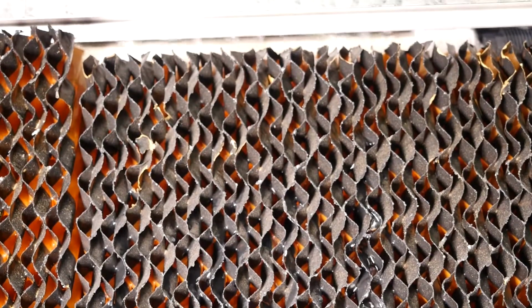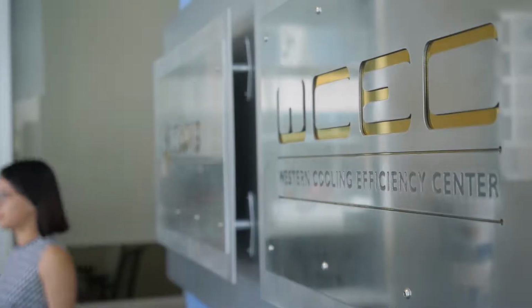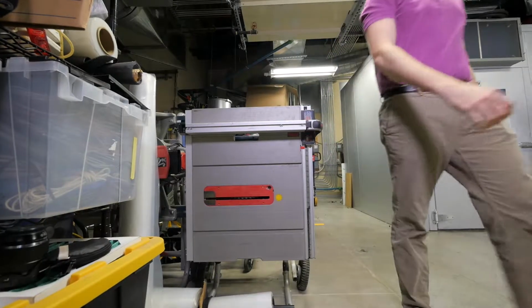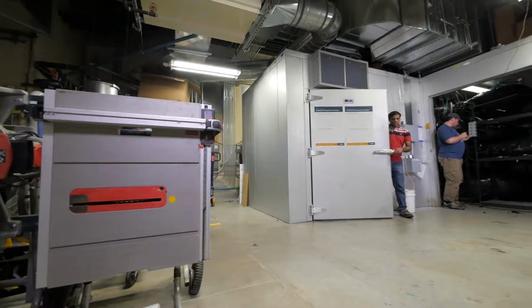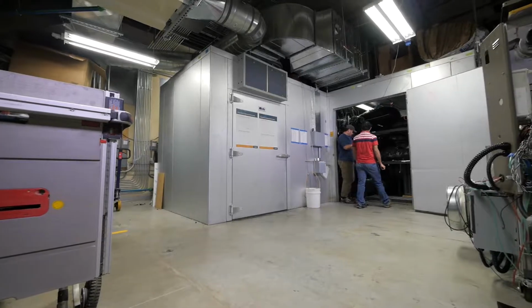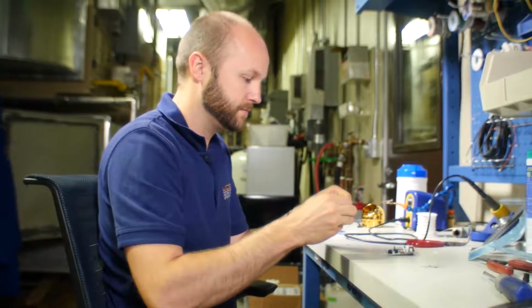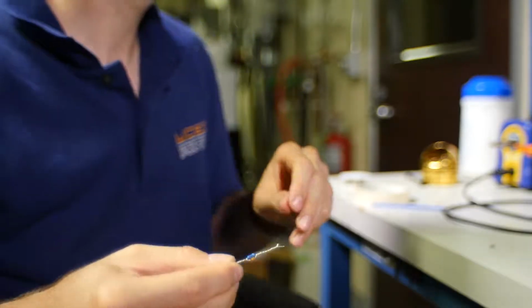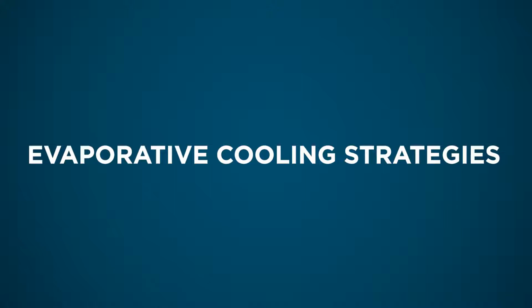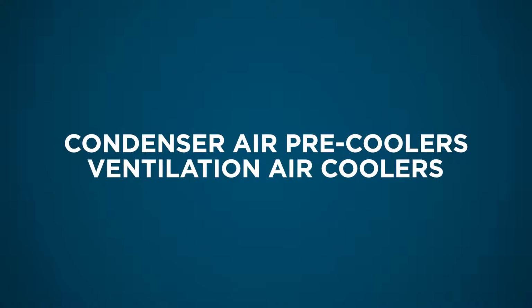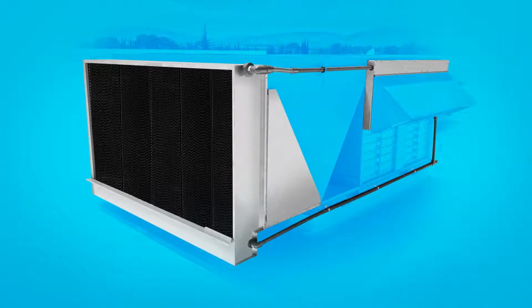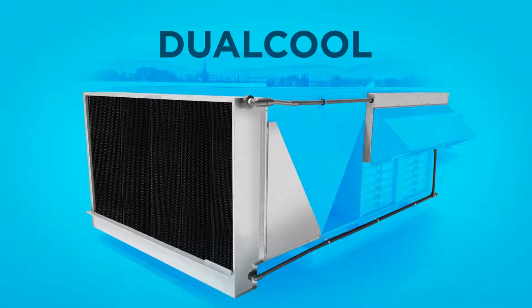Numerous modern evaporative technologies have proven effective through third-party testing, and customers are reaping the energy savings they deliver. One such third-party testing facility is the UC Davis Western Cooling Efficiency Center, or WCEC, the makers of this video. The WCEC researches, develops, and demonstrates technologies, including evaporative cooling technologies, that address both overall energy consumption and peak demand. A variety of evaporative cooling strategies exist for commercial buildings, and they can be categorized into two broad groups: condenser air pre-coolers and ventilation air coolers. This video will explain one evaporative cooling product called DualCool, which combines both strategies.